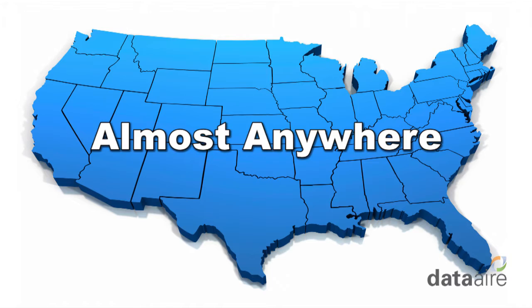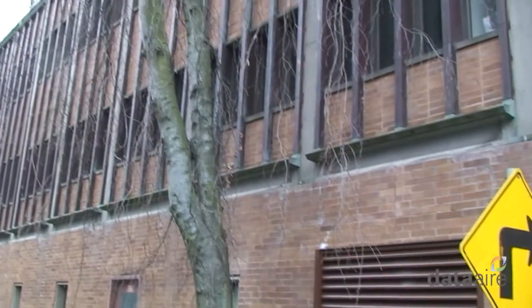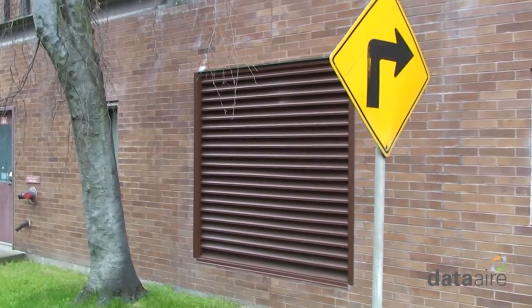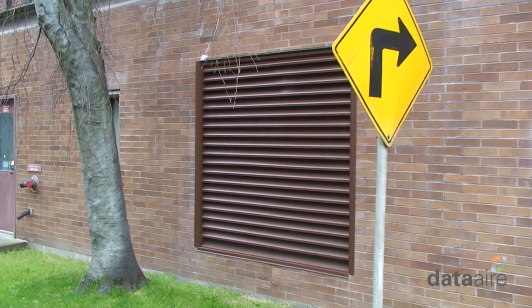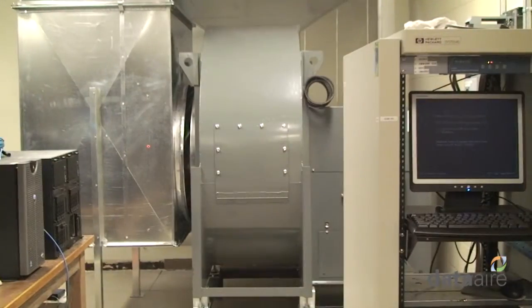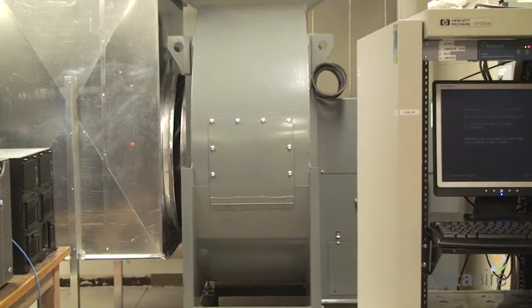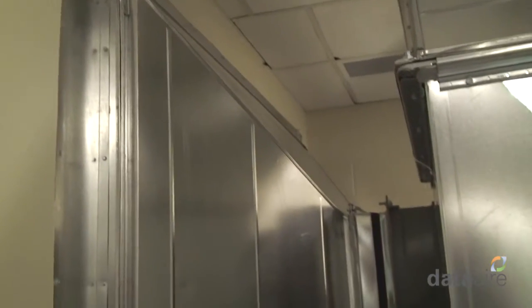Except Florida. All Air Side Economizers must have access to an outside air source and a way to relieve pressure buildup in the room, such as a pressure relief fan. These louvers, ducting, and fans are supplied by third-party vendors.